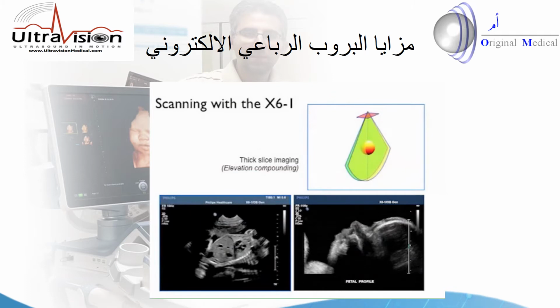One of them is to, instead of making a very uniform thin slice, make a uniform but slightly thicker slice. And this so-called elevation compounding, or thick slice imaging, reduces speckle and increases contrast resolution, allowing you to see with better clarity structures of near equal echogenicity.